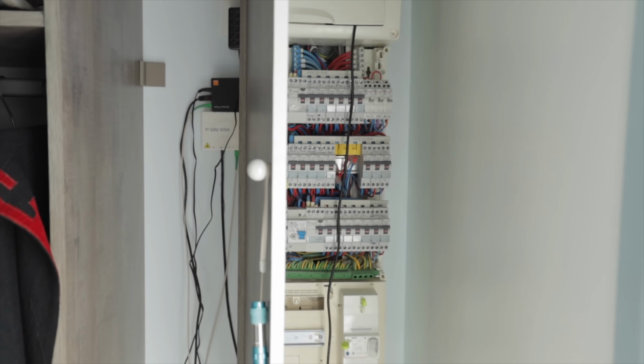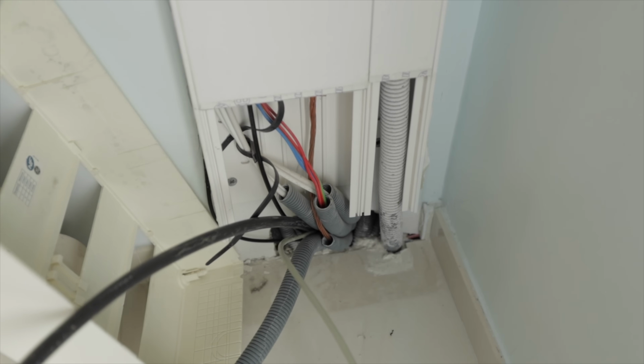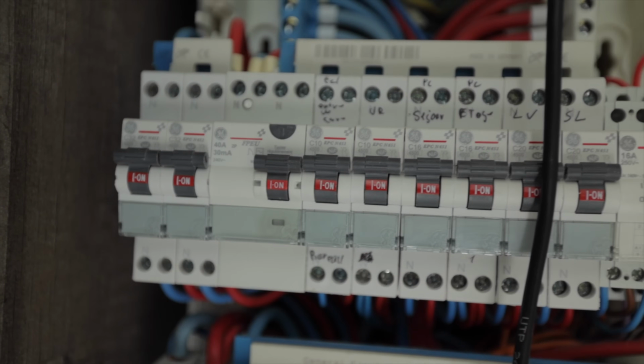The other difference is the consumer unit. We didn't really end up showing much about the connection in the consumer unit, but you use double pole breakers, right? Always. Double pole MCB is compulsory. So we use double pole RCBOs, but for an MCB, just a normal disjoncteur that just does overcurrent, it's only single pole in the UK.